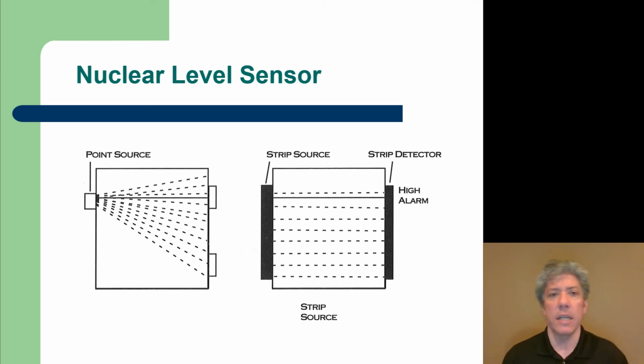That's the idea here. And so in the first image on the left, a point source of radiation is being used, and there's just a high and low detector. If all we really care about is not so much the actual level in the tank, but whether it's high or low, then this is an on-off type of sensor that would work fine. And just think of this as a flashlight, okay, where you're detecting how much light makes it. If a lot of light makes it through to the top detector, then there must not be liquid in the way, right? But if a lot of light makes it through to the bottom detector, there must not be liquid there either, right? And so that would indicate a fairly low level.